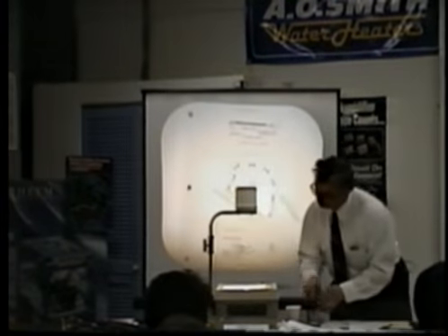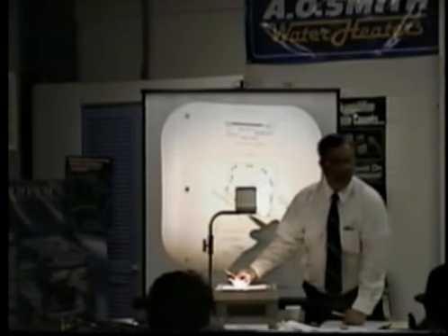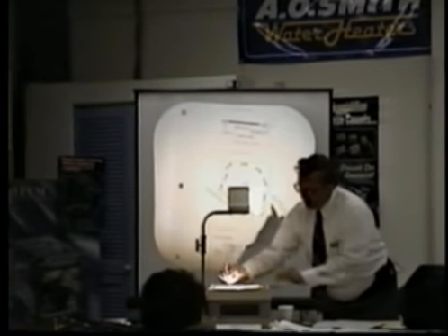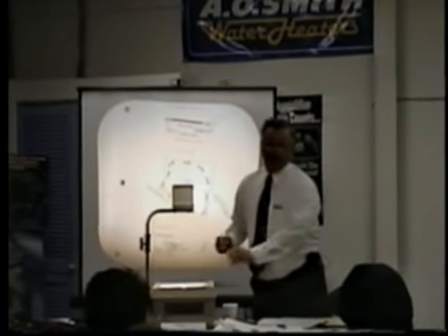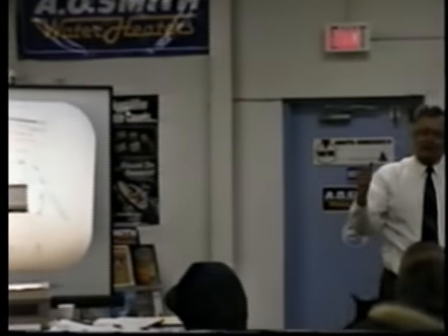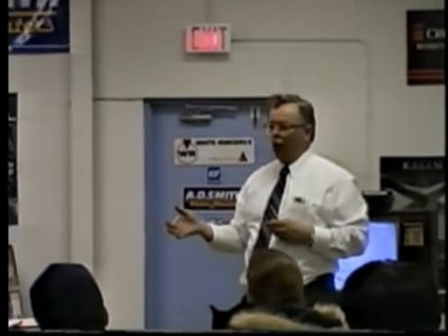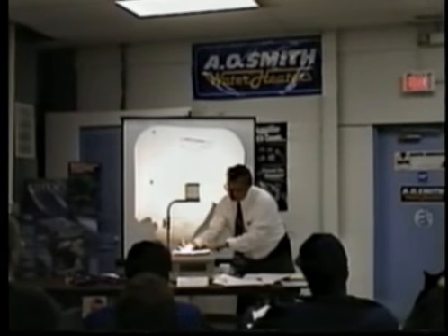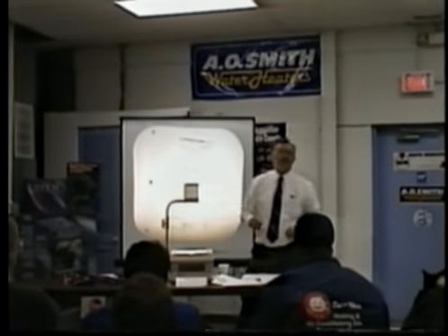Ladies and gentlemen, watch. If this is like a vacuum cleaner, and we're moving air, if I drill a hole in my return, because it's pulling on the return, and I take a piece of tissue paper and put it over the hole, does the piece of tissue paper get blown away or sucked in? Because it's pulling and it gets sucked in, we call that negative pressure.